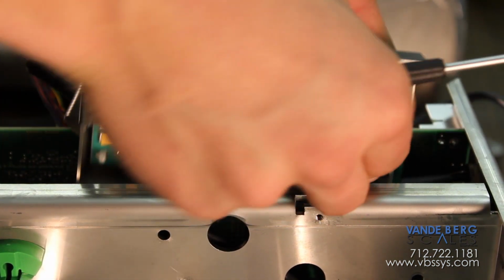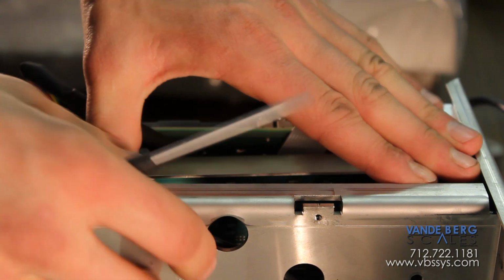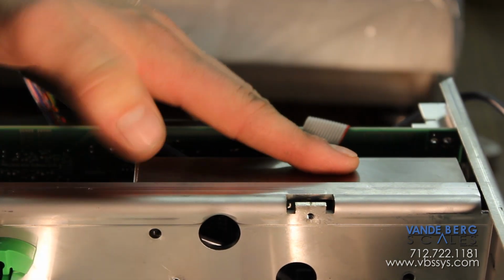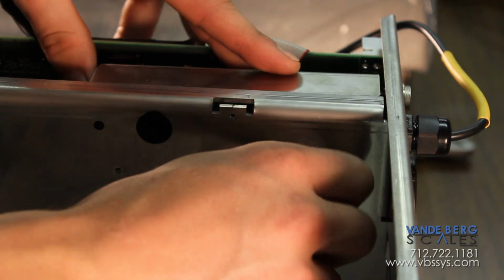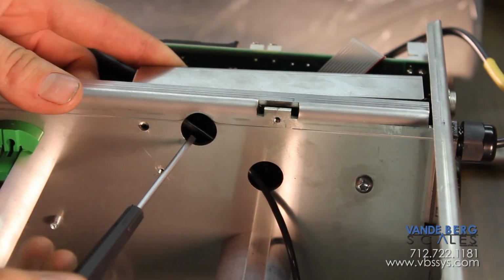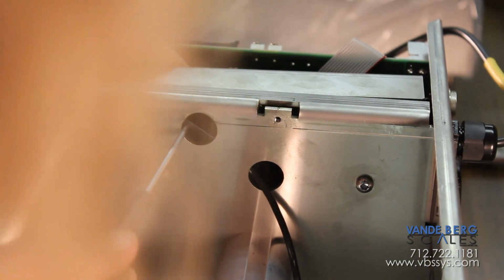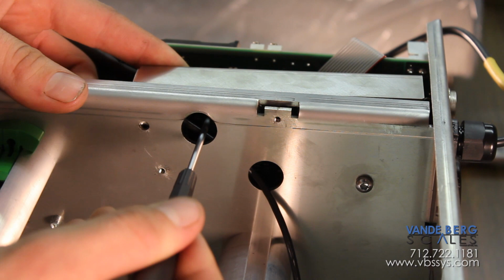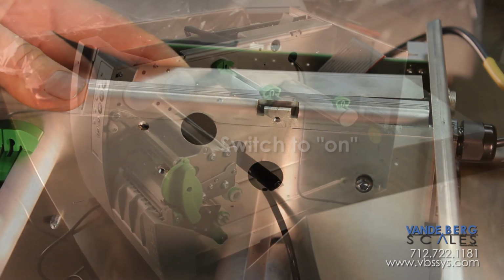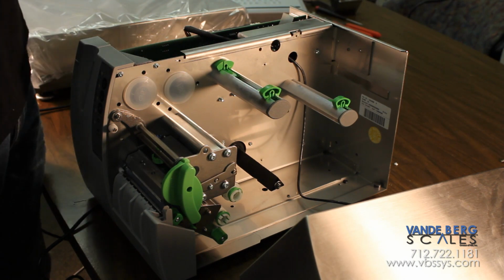Once you're done wiring up your load cell, you can put your A to D card back in its spot and screw it back in. Through this hole, you'll see a little switch in there. This will need to be switched for calibration. This will be the seal switch. We can start putting it back together now.